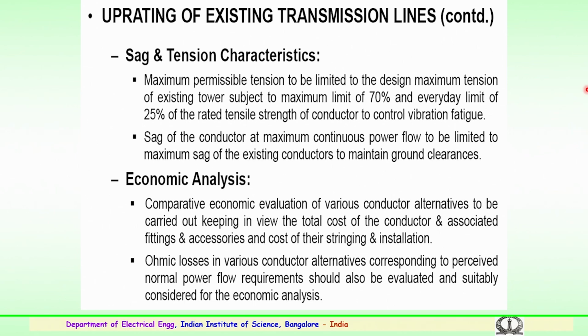total cost of the conductor and the associated hardware or accessories, and the cost of the entire stringing and the new installation. An important point to be considered is the ohmic losses which could occur in various conductor alternatives corresponding to the perceived normal power flow requirements. These should also be properly evaluated, and suitable considerations are to be made for the economic analysis.